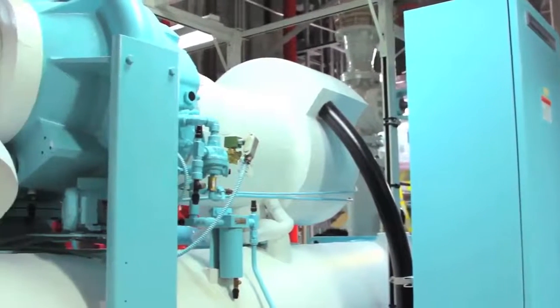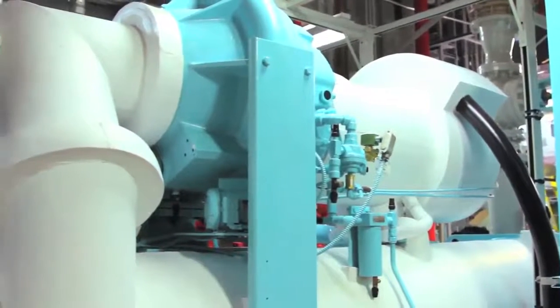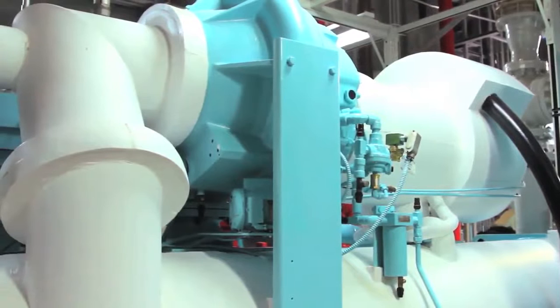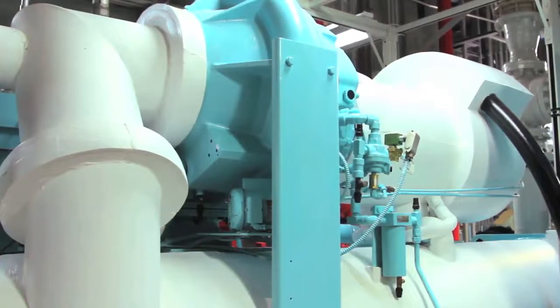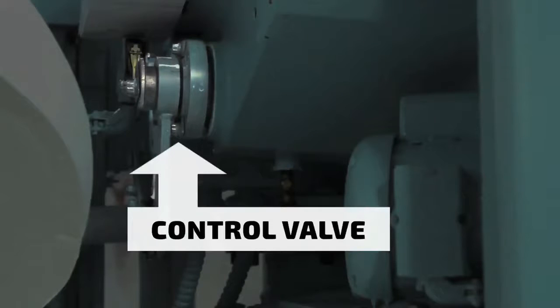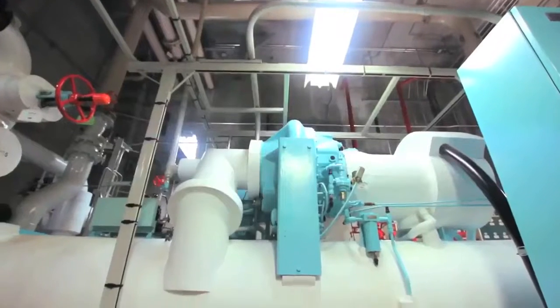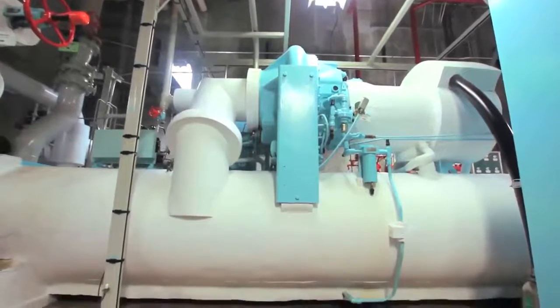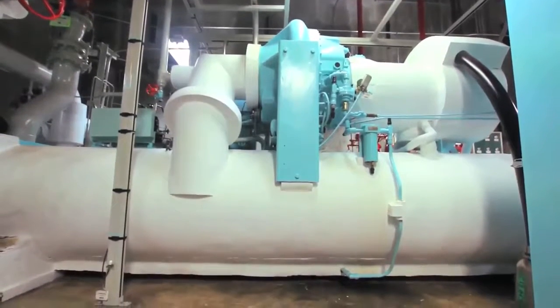On the inlet side, there's a large impeller. Prior to the impeller is a set of inlet vanes in an annular configuration, which the control system will open and close to regulate the inlet volume into the compressor at the impeller. The hot compressed gas is then discharged, so we have to cool and condense that gas.